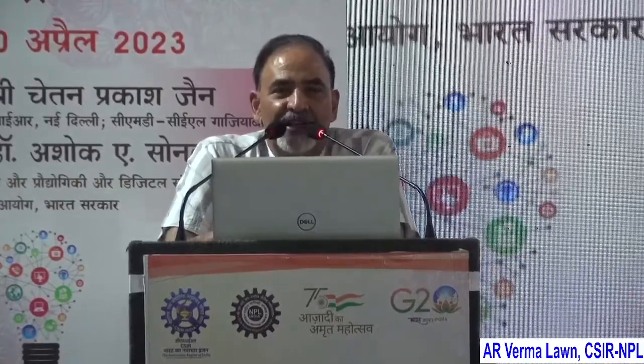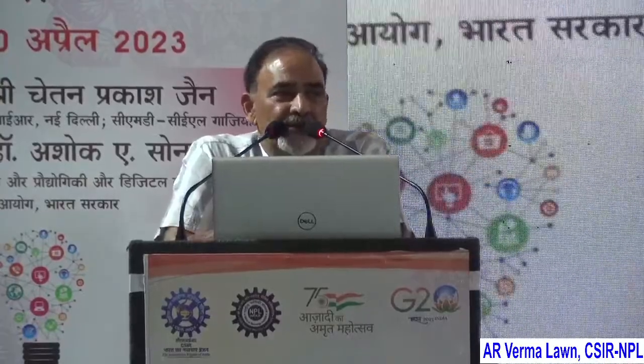So this was the first instrument, and another change which we proposed in our instrument was, in the imported instruments one has to do only particulate sampling at a time, and do the gaseous sampling next time. What we did, we extracted a sample from the stack in two streams. One was going to the filter paper, the other was going to the gaseous sampling impingers or the absorbing solutions. So at the same time one can do the particulate sampling as well as the gaseous sampling.